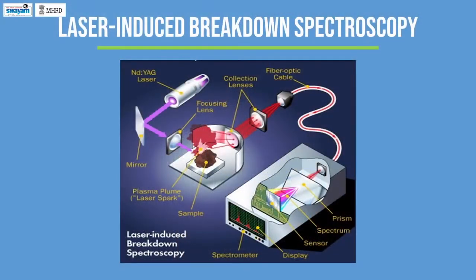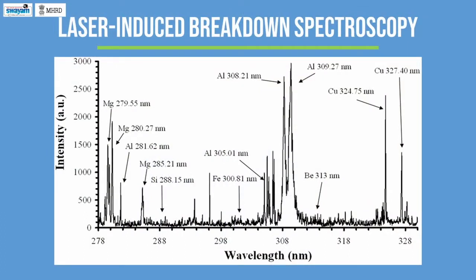This is a schematic diagram of a typical LIBS system. The LIBS system consists of a solid state laser, sample holder or stage, monochromator, detector, and other optical components such as focusing and collecting lenses, mirrors, etc. This LIBS system is generally coupled to a computer which can rapidly process and interpret the acquired data. The LIBS spectrometer gives a two-dimensional graph depicting the variation of emitted light intensity with respect to different wavelengths, typically from 170 nanometers to 1100 nanometers.